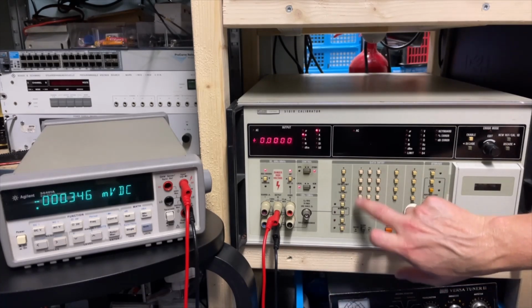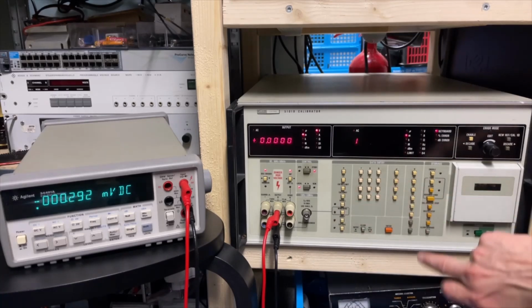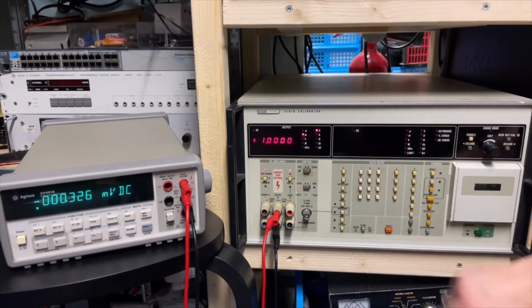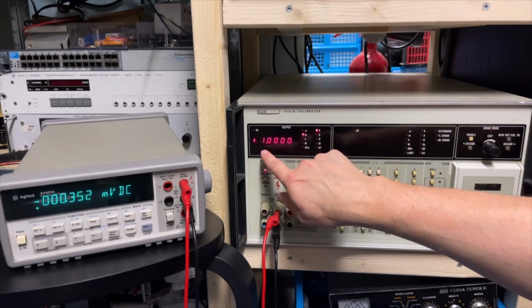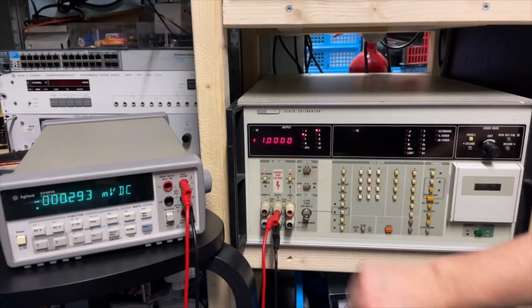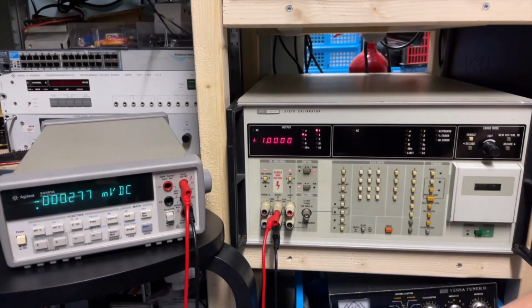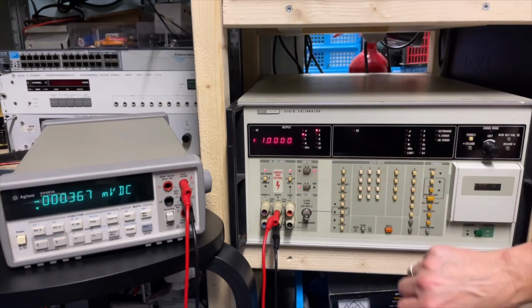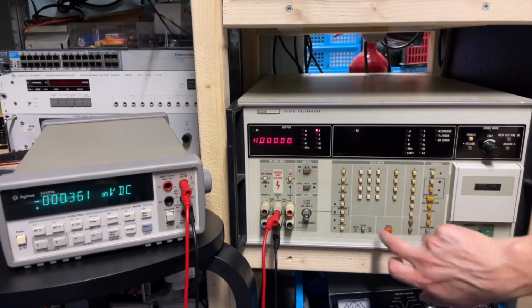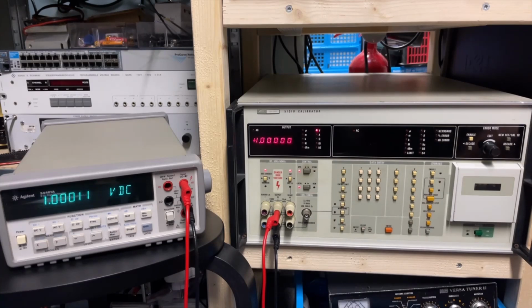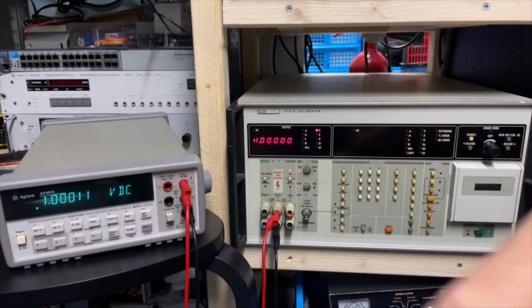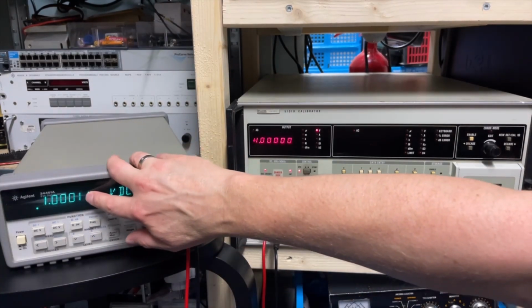And the data entry. Let's see, 1 millivolt. Enter. It goes here, bloop, the entry, and then it says not AC, so that probably means it's DC, and then we have 1.000 millivolt. Is that true? I would say that is almost true. Perfect. It's a fractional off. And what if we do 100 millivolts? I did 1 volt apparently. Okay. So it is a little bit high, but it hasn't been switched on very long. And well, for a 3.5 digit multimeter you would be happy with this, because this is then your last digit. That is usually the plus minus.